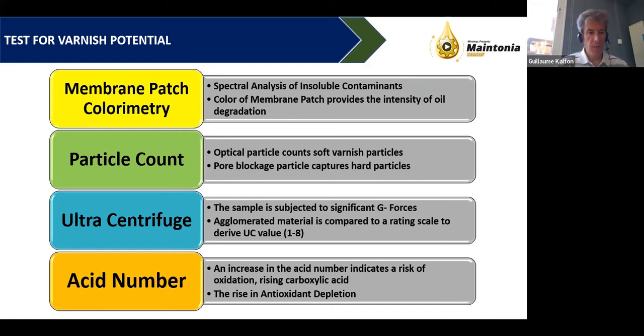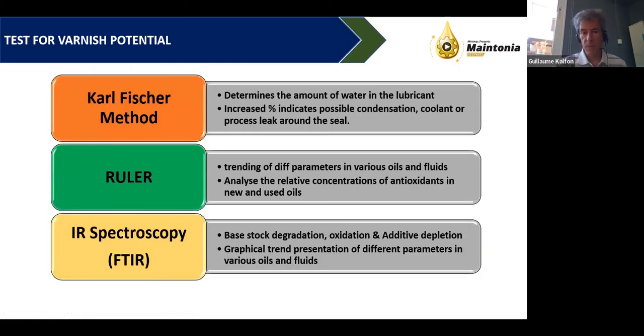So if you have to send a sample to one lab and for some reason send a sample to another lab, you're able to compare both results because it's a standard D7843 method. So that's very important. So all in all, the test that is needed, that is by far the most commonly used for this problem, is the MPC test. And if you want to protect your equipment from this phenomenon, the MPC test is basically a test you need to have on your oil analysis report.